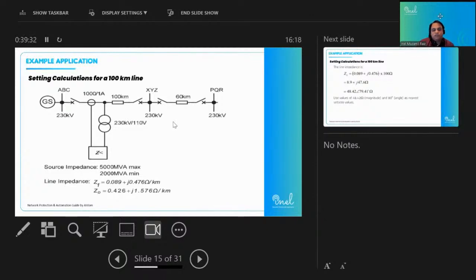Why are we using this zone-based approach? This is because we need main protection. Main protection will be for this line section. And we also need backup protection. Like if the relay at this location, which is for the XYZ, fails to operate, then we should have a backup protection from this ABC side. After some time, which is pre-decided, in our case 300 millisecond, if this relay is not operated, or there is a stuck breaker condition at this point, then this ABC relay will provide backup protection for this section of the line. So it will isolate the faulty portion also.